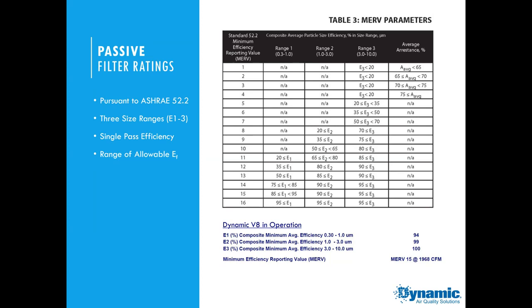The dynamic V8, which is what we would use in a MERV 13 or greater situation, would have less static pressure and a far lower energy consumption than a MERV 13 filter. We're going to be 99% efficient in that critical 1 to 3 micron range.